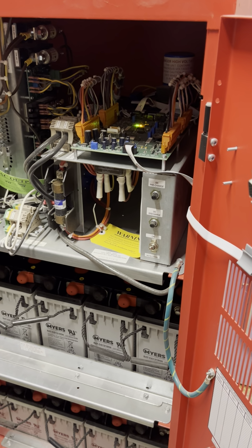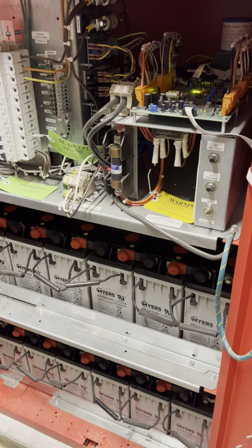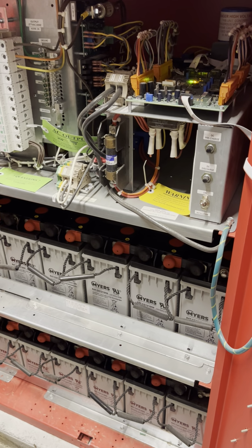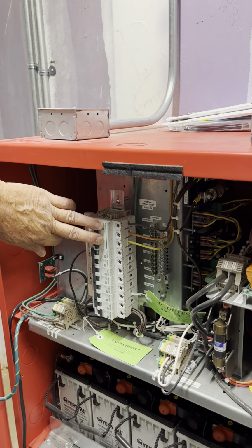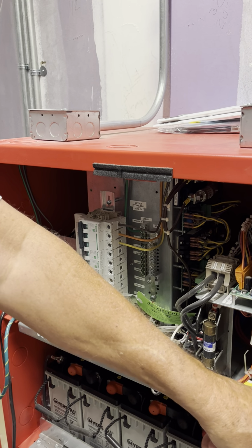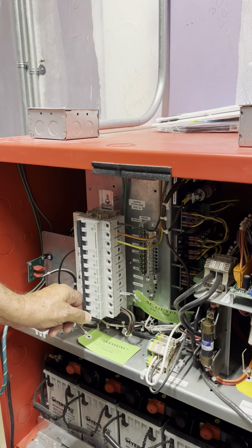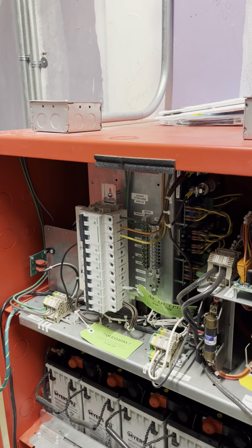So if any time while you're here and you're having a problem, let's say you come in, you smell the batteries, it's a distinct smell, I'm sure you've probably smelled before, and you need to shut the system down, what you want to do, there's nobody in the church, right? Okay, shut off your output breakers, shut off your isolation switch, turn off your input breaker.